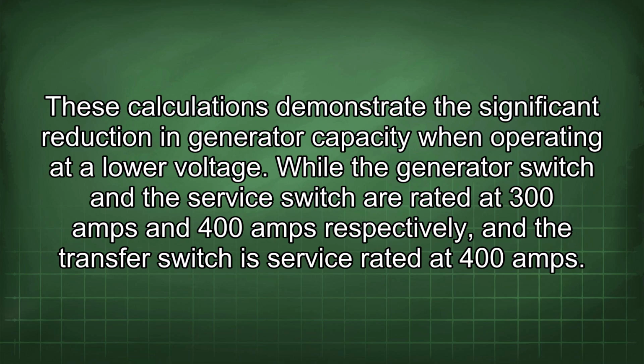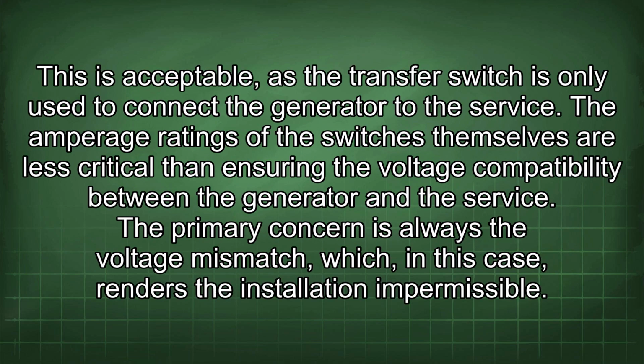While the generator switch and the service switch are rated at 300 amps and 400 amps respectively, and the transfer switch is service rated at 400 amps, this is acceptable, as the transfer switch is only used to connect the generator to the service. The amperage ratings of the switches themselves are less critical than ensuring the voltage compatibility between the generator and the service. The primary concern is always the voltage mismatch, which, in this case, renders the installation impermissible.